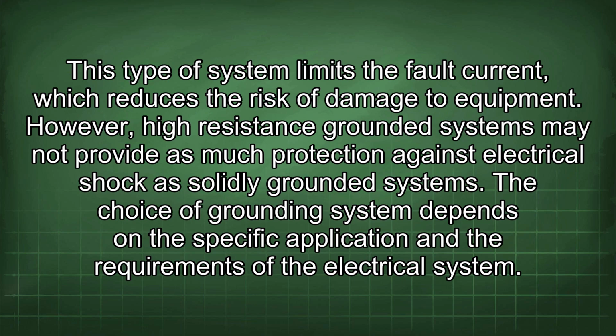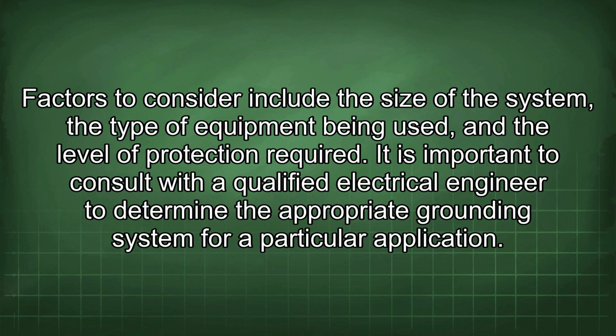However, high-resistance grounded systems may not provide as much protection against electrical shock as solidly grounded systems. The choice of grounding system depends on the specific application and the requirements of the electrical system. Factors to consider include the size of the system, the type of equipment being used, and the level of protection required.